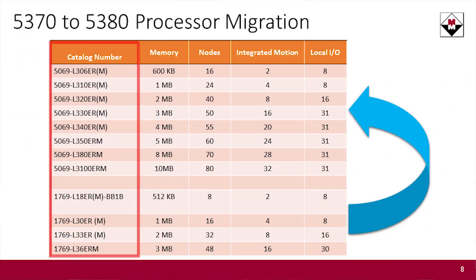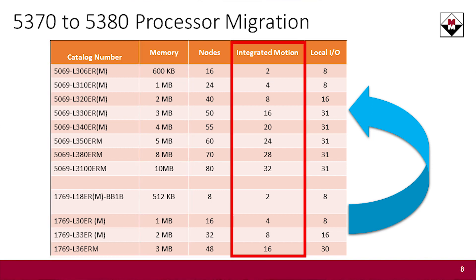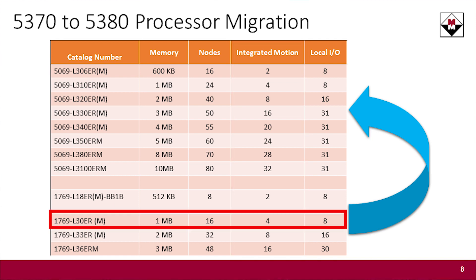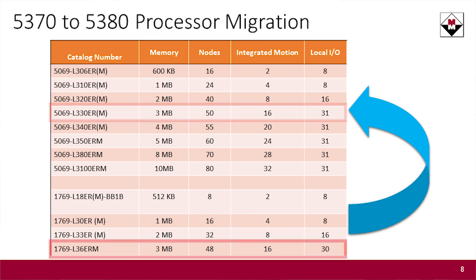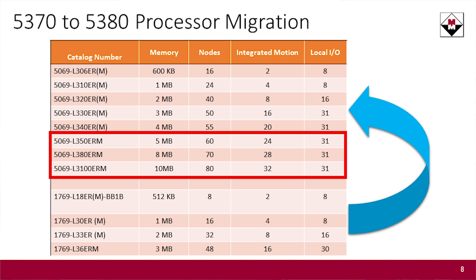When you're comparing the old 5370s to the 5380s, you actually have more part numbers available now — they've spread out the amount of memory, the number of network nodes, and the number of integrated motion axes it can support. Typically, an L30 would migrate up to about an L330. An L36 would probably migrate up to a 350 through a 3100, depending on how much memory you needed. That's the biggest difference there.